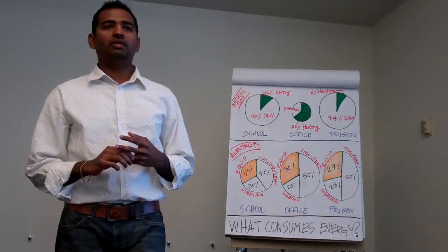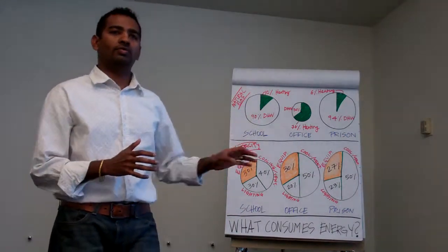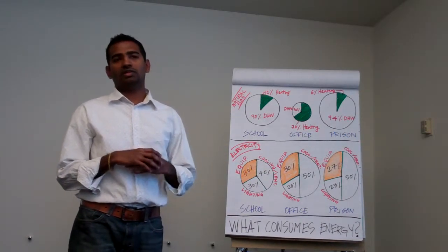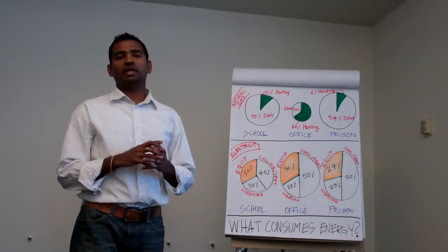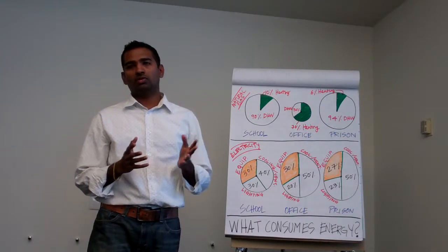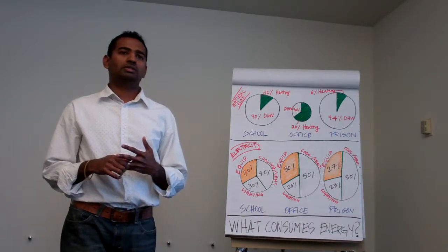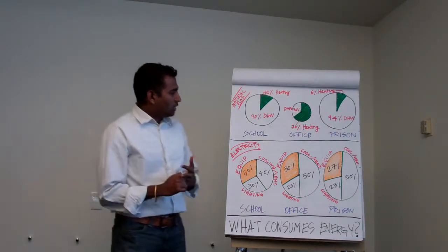Typically, when we design solar hot water for any building, we always design for about 60% or 70%, because we cannot completely rely on solar hot water. What if the sun's not there during the coldest months? You're screwed, right?